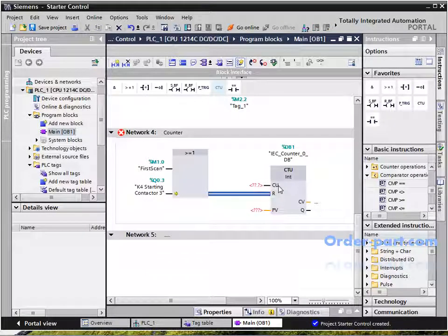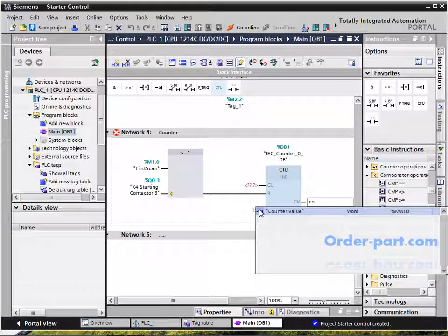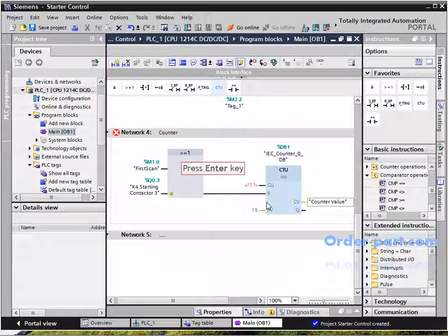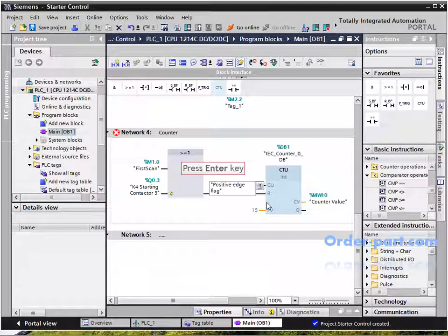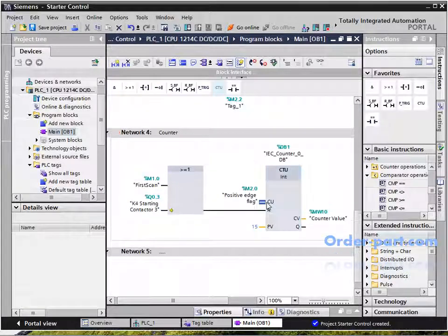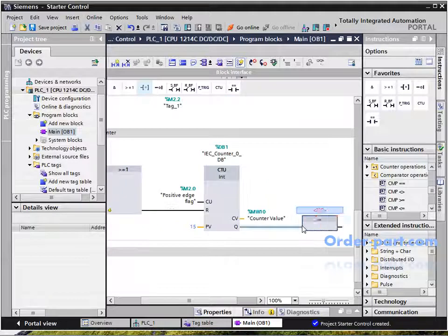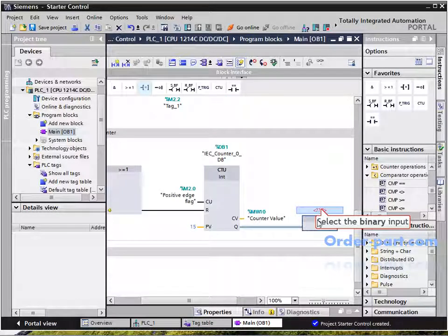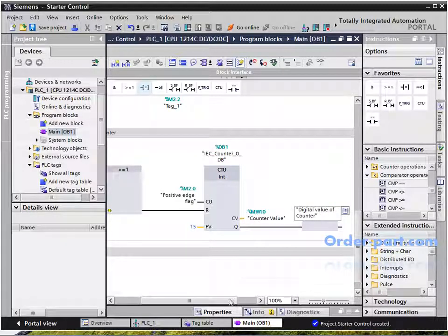In Network 4, the counter gets reset at the start of the PLC — that is, on first scan — or on the closing of K4 contactor. The M2.0 pulse from Network 3 increments the counter every second, and the numerical value of the counter is stored in MW10. M2.1 gets set when the counter reaches 15.